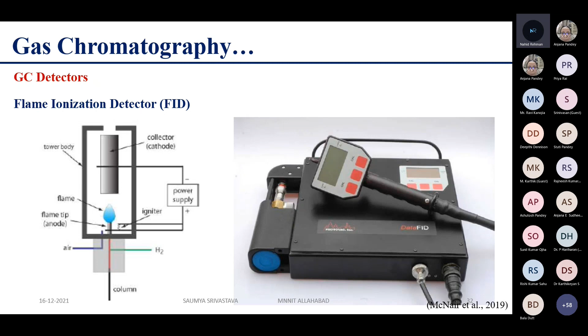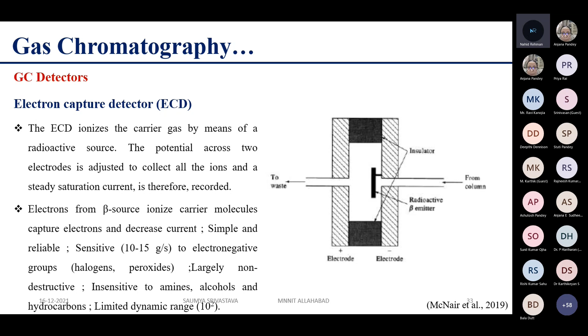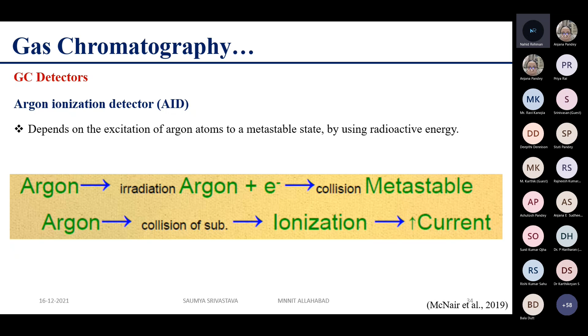Then there is the electron capture detector, which ionizes the carrier gas by means of radioactive sources. Potential across the two electrodes is adjusted to collect all the ions, and the steady saturation current is therefore recorded. In the ionization detector, the ionization strength changes when the solute comes in, and this is converted into an electrical signal inside the detector. Another detector is the argon ionization detector, which depends on the excitation of argon atoms to a metastable state using radioactive energy.